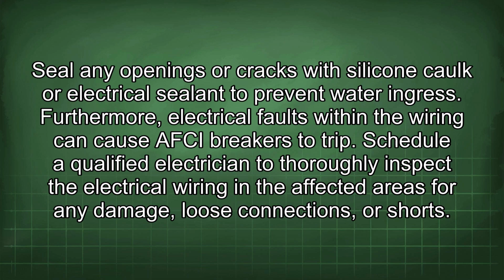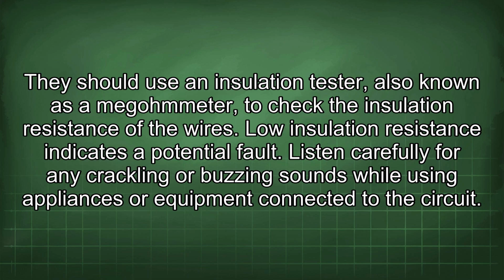Furthermore, electrical faults within the wiring can cause AFCI breakers to trip. Schedule a qualified electrician to thoroughly inspect the electrical wiring in the affected areas for any damage, loose connections, or shorts. They should use an insulation tester, also known as a megohmmeter, to check the insulation resistance of the wires. Low insulation resistance indicates a potential fault.